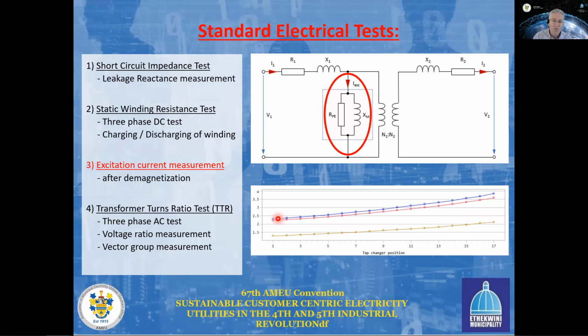And also for increasing tap position, the excitation current should increase, because as you are increasing your tap position, you've got less winding, so you need more current to energize that transformer. That's why this current is increasing with increasing tap number.